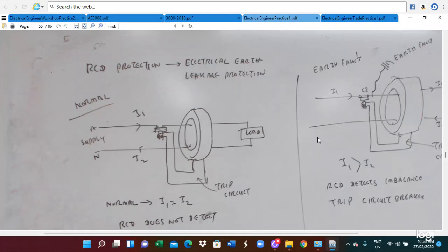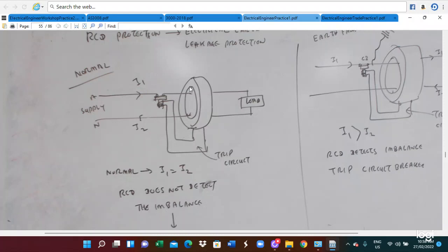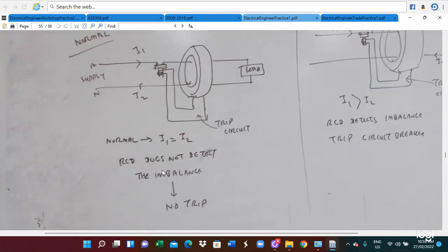We are now looking at the Residual Current Device, or RCD. An RCD is a residual current device. When electrical current flows, current I1 goes from the supply to the load, and current I2 returns from the load to the supply. Under normal conditions, I1 equals I2, so the RCD does not detect any imbalance current and does not trip.